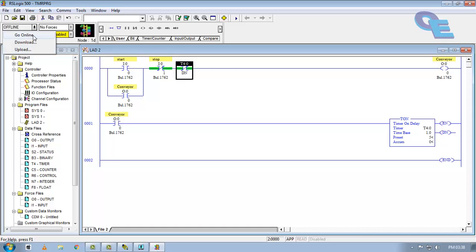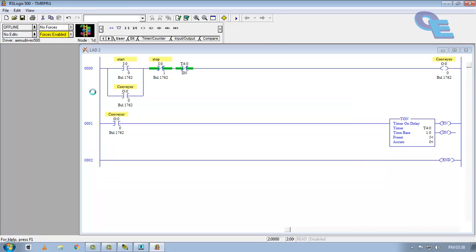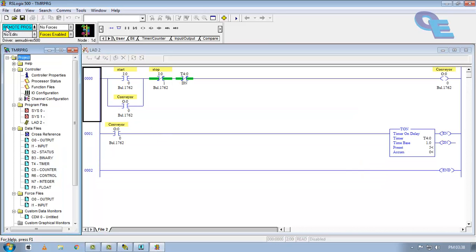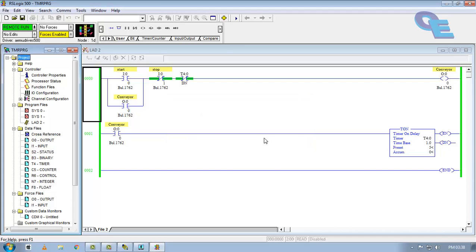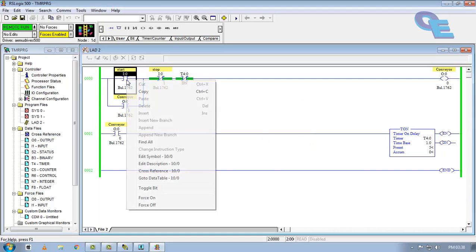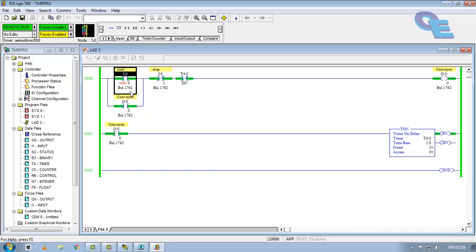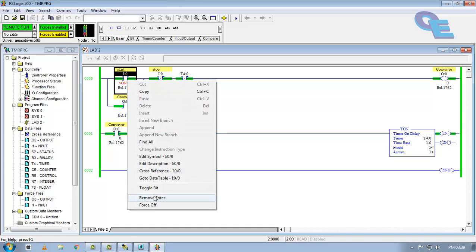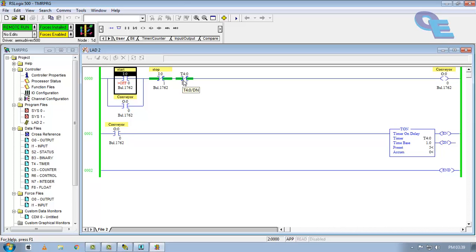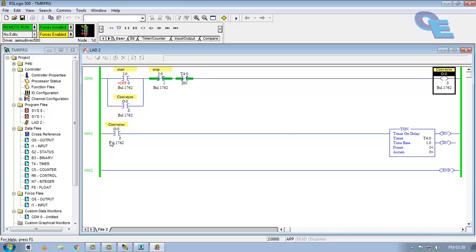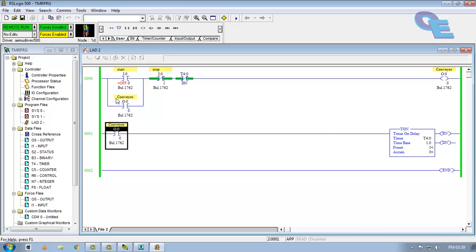Now go to online and run. Now I am triggering this input, force on. Here you can see 3, 4, 5. After 5 seconds the done bit is going to be high and this normally close contact is going to be open. So conveyor is off, means the input of timer is also off.